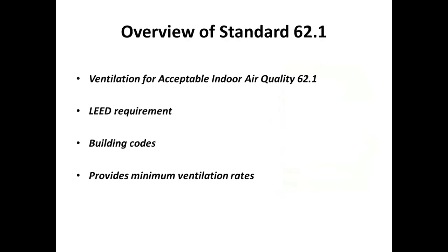62.1, as I mentioned, really focuses on ventilation. Buildings, in order to get LEED certification, must meet ASHRAE standard 62.1. This is factored into a lot of building codes now. Essentially, it's providing minimum ventilation rates for unoccupied spaces on a per square foot level, and increasing those minimum ventilation rates as you have occupancy in a building.